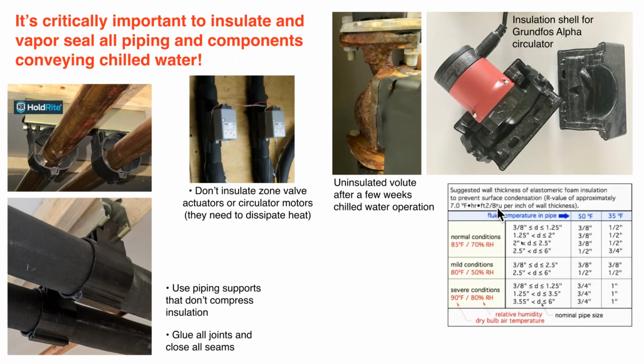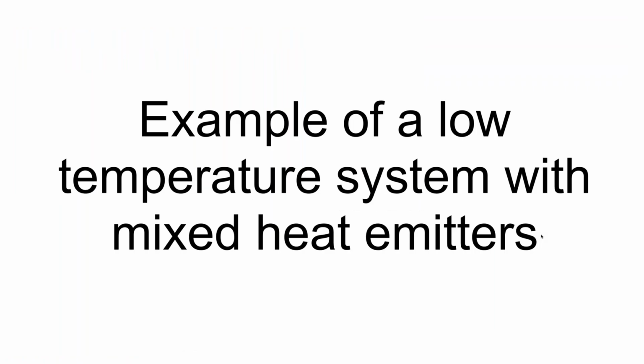Here's a table if you're looking to insulate piping with standard elastomeric foam insulation. Depending on the fluid temperature and what the surrounding air conditions are, it shows some minimum thicknesses of insulation, and it also depends on the pipe size. Okay, so again, chill water works great for cooling. Just make sure you do a good job with that pipe insulation.